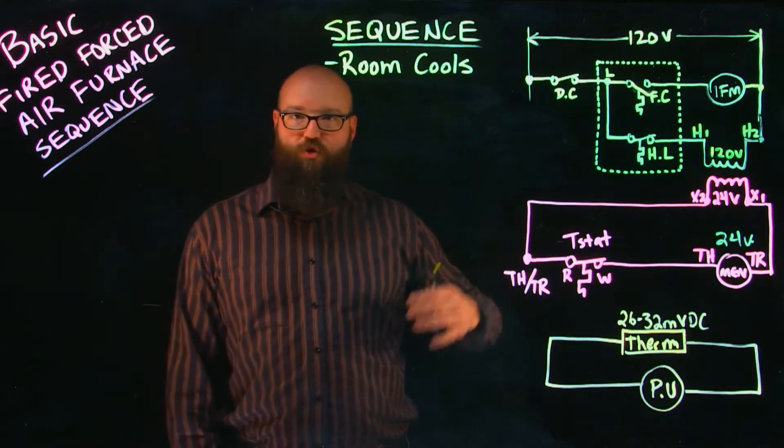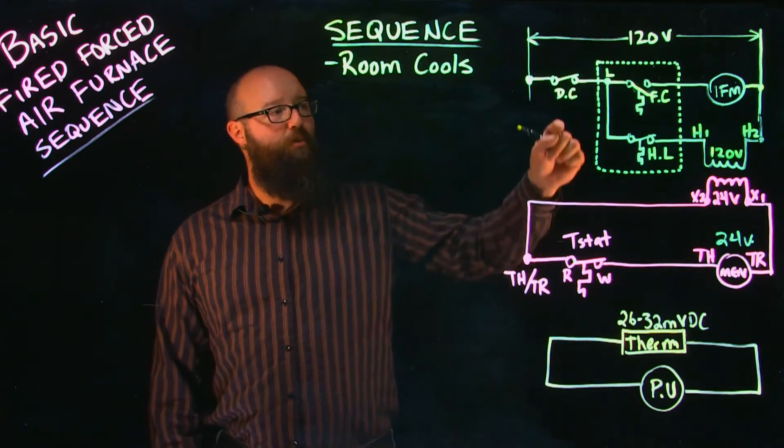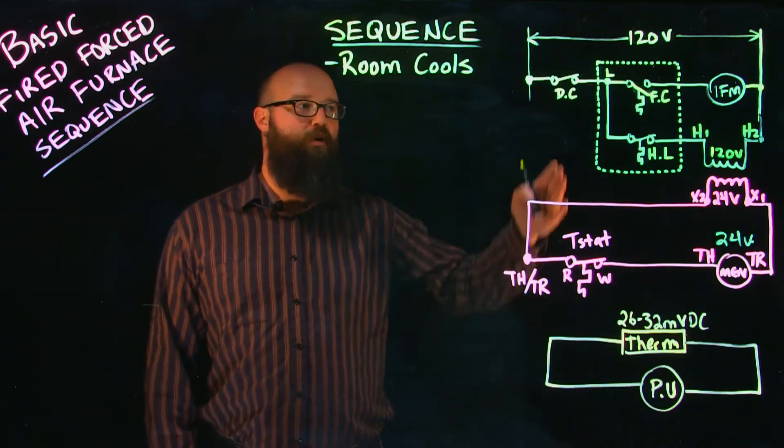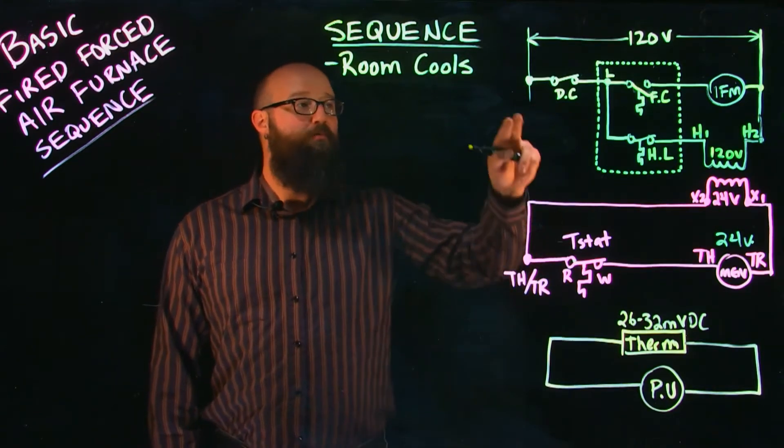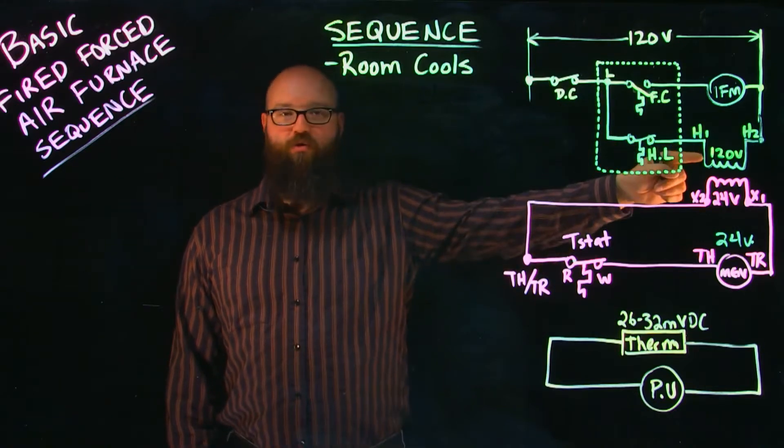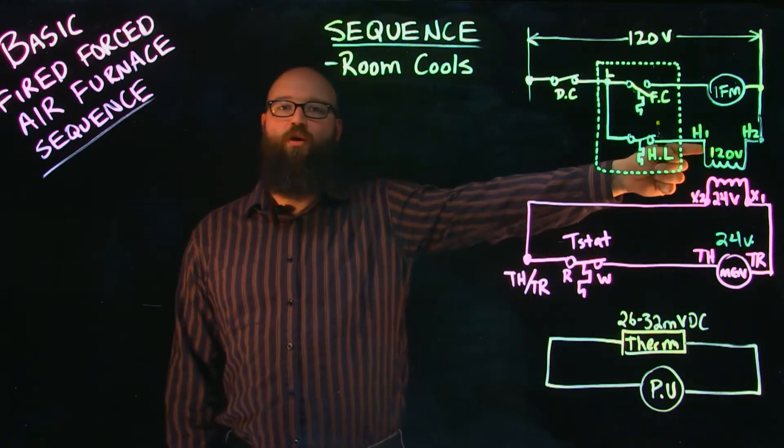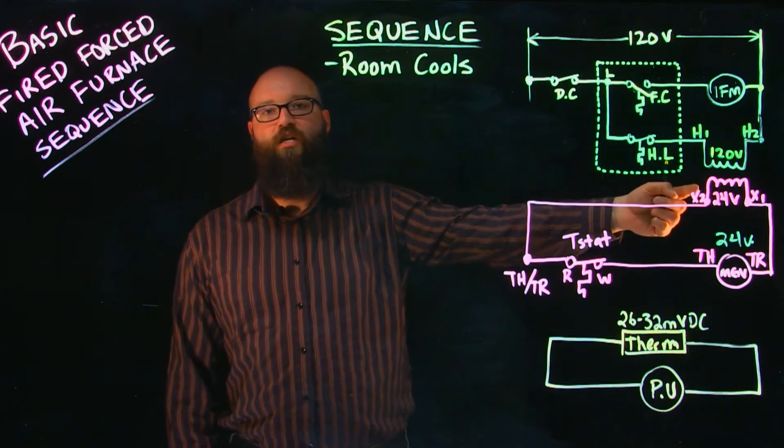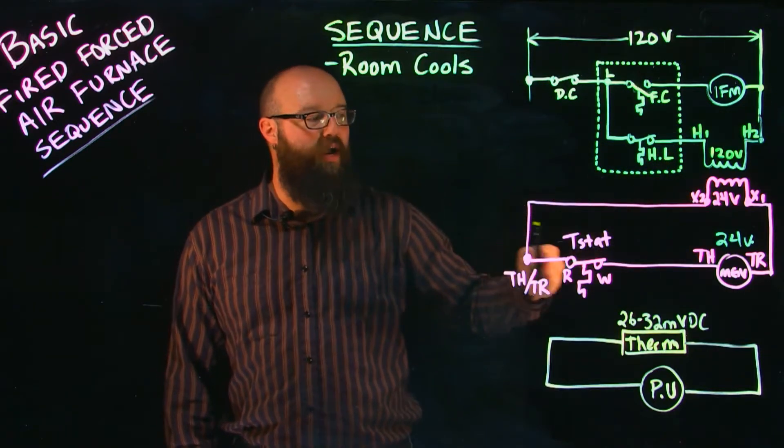Now a couple of points to show you before we get rolling here. My disconnect I've got shown in the closed position which would normally be shown on a schematic in the open position, but we can see I have power through my high limit to the 120 volt primary side of my transformer which I have 24 volts on the secondary of my transformer which feeds my control circuit.